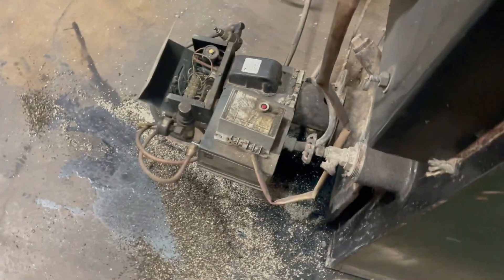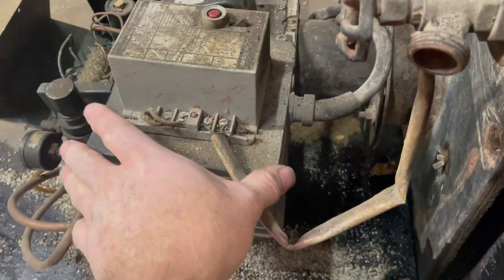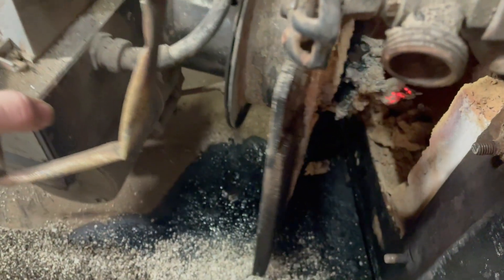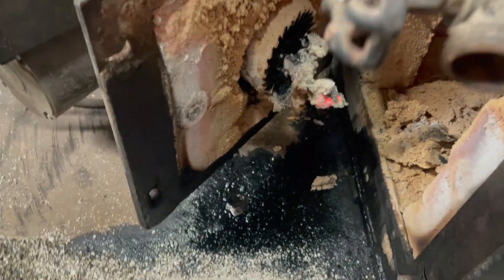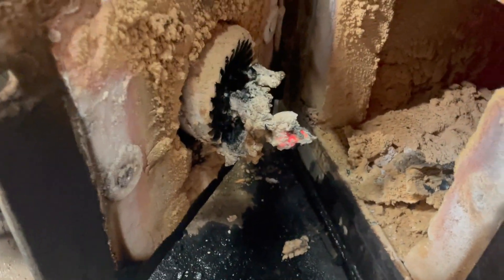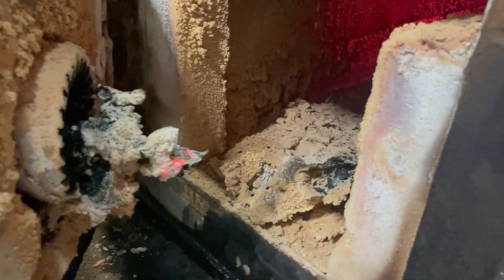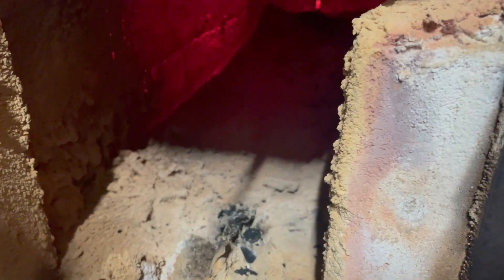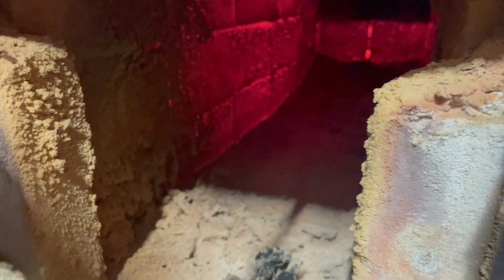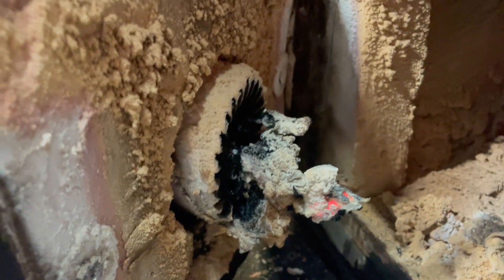This is a Fire Lake burner — the best waste oil burner ever made — and it's a Columbia boiler with a swing open door. I just wanted to show you what happens here. This is a product of synthetic oil. We didn't have this five years ago, but now today we call it the volcano. It's normally a lot prettier than this, more organized. A big buildup gets right in front of the flame and then it causes chaos to the flame. If you look here, none of that stuff there belongs.